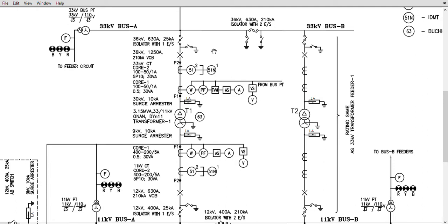Let's say in our case, 33 kV, we are using a vacuum circuit breaker, which means the vacuum is the arc quenching media, so that there will not be any spark when we break the circuit with the help of the circuit breaker. Vacuum means nothing, and hence the spark will not continue, will not travel between the terminals. So this circuit breaker, apart from operating on load conditions, in abnormal condition can be operated by its own. Its own means with the help of CT and relay.